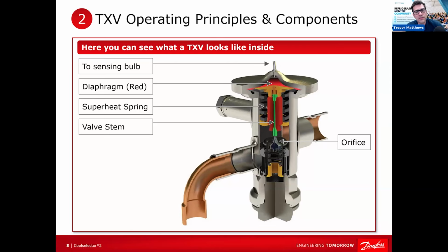Were your old valves, like 15, 20 years ago, all stainless steel, and you guys changed to copper, or was it? No, it's always been a stainless steel body, cap tube, and sensing bulb. And we always had that bimetal connection just because it's just 10 times better. I'm not saying we never had a stainless steel valve, but not a TXV that I'm aware of.